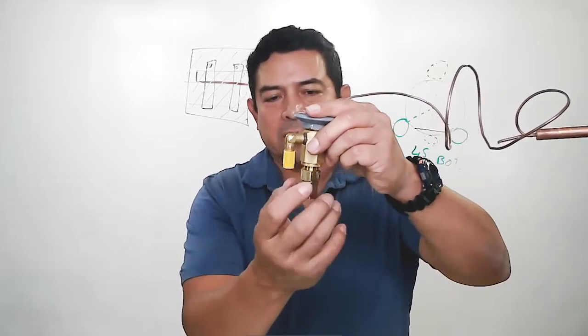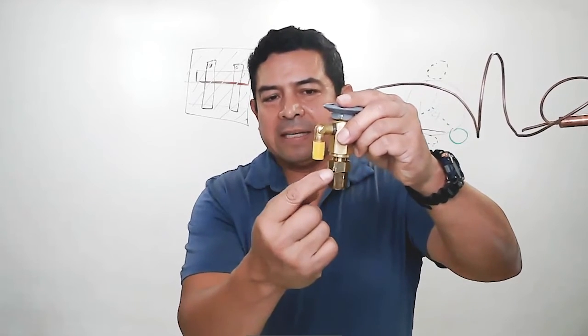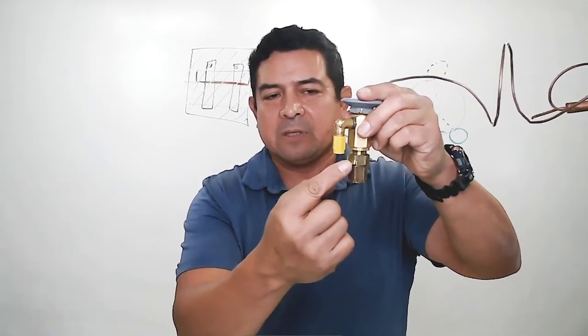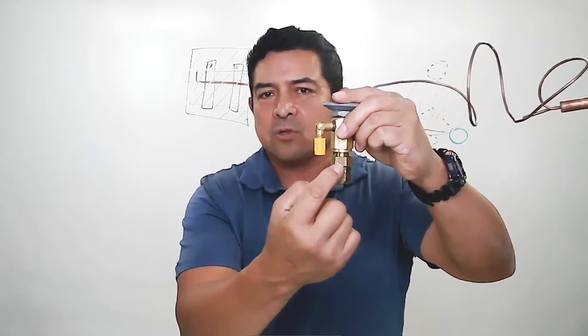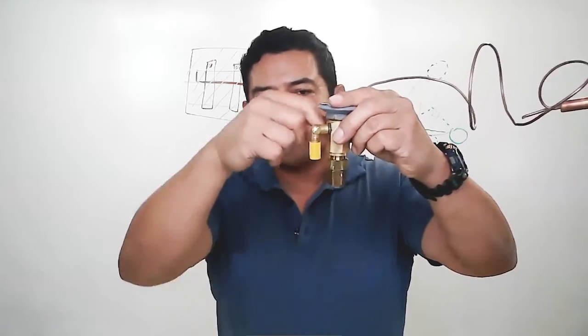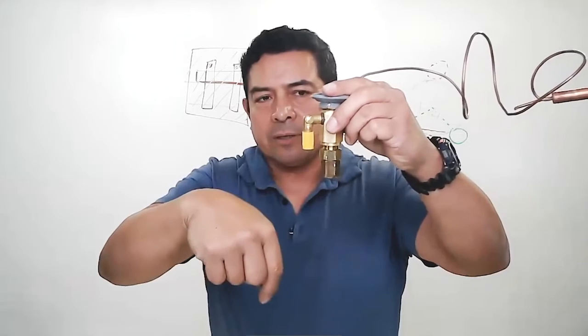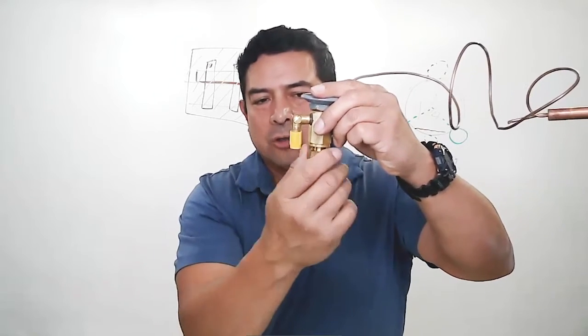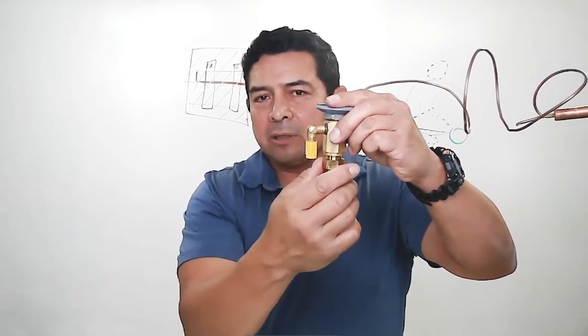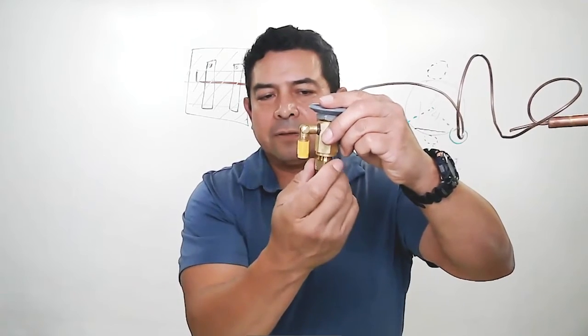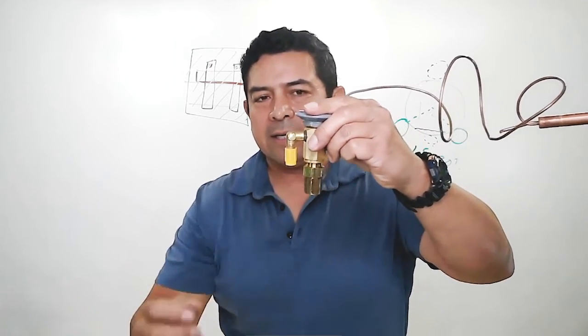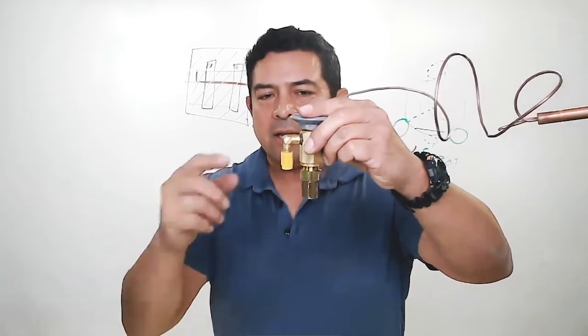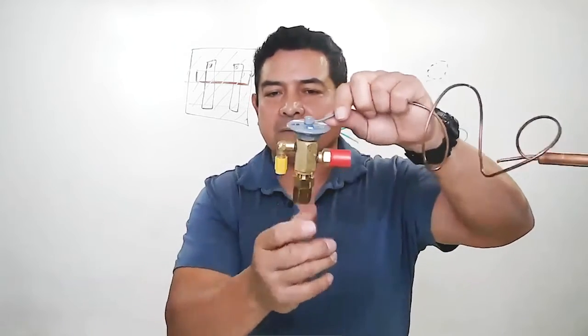You don't take this apart. In here, you have a seal of some kind. Sometimes they use Teflon, sometimes they use rubber to make sure that the pressure does not leak out this way. So what happens is you leave this in there, you're going to melt all of that. So you need to take this off, you need to remove it, set it aside, take the pins out, and then you can install your TXV in place.